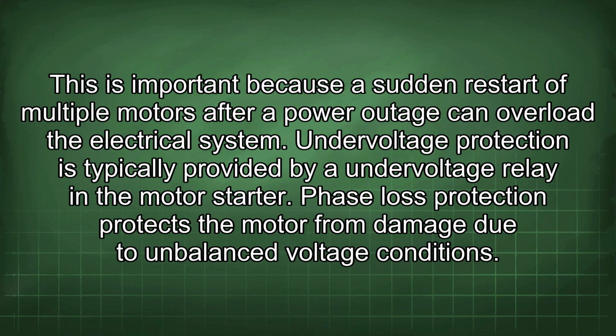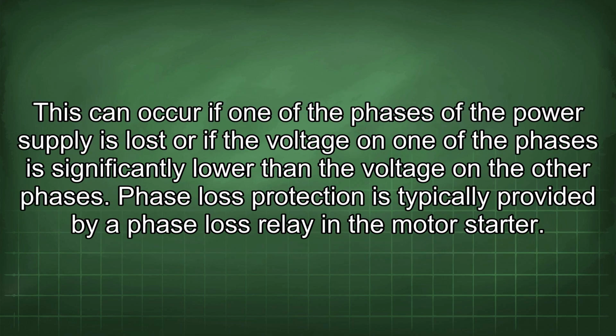Phase loss protection protects the motor from damage due to unbalanced voltage conditions. This can occur if one of the phases of the power supply is lost or if the voltage on one of the phases is significantly lower than the voltage on the other phases. Phase loss protection is typically provided by a phase loss relay in the motor starter.